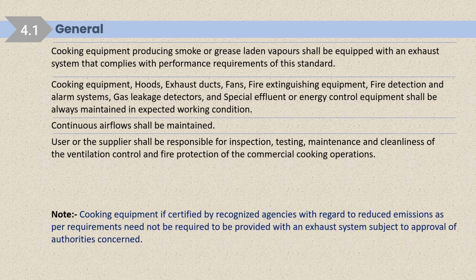One note I have added here: cooking equipment, if certified by recognized agencies with regard to reduced emission as per requirement, need not be provided with an exhaust system, subject to approval of the authorities concerned. So there are some equipment available in the market which is certified by a recognized agency with regard to reduced emission. If it is there, then there is no requirement to provide the exhaust system.